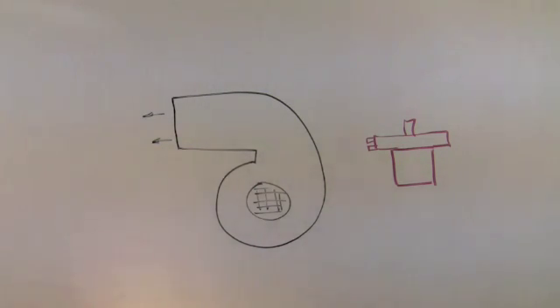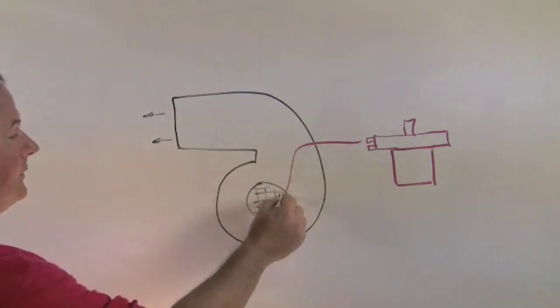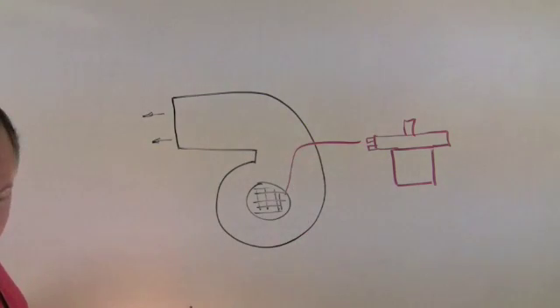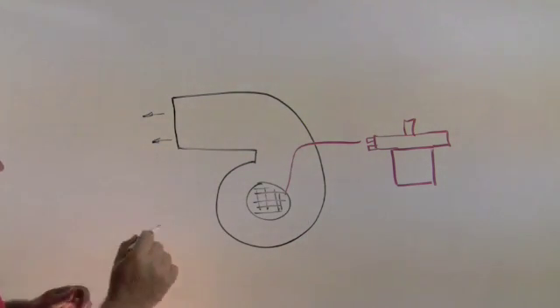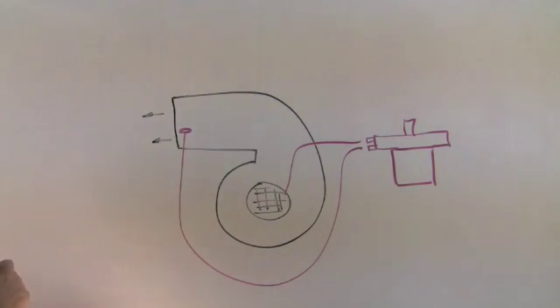Here's a little graphic on how it's set up. We have a fan, here's our airflow switch. Low pressure port hooked up before the blower, high pressure port goes up to the high pressure side of the blower. We're now taking a differential measurement across that fan and know for certain whether it's running or not.